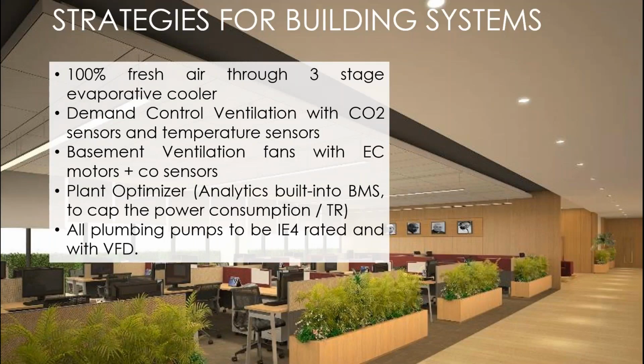also to add, when we talk about variable frequency drives, in indoor air handling units they have VFDs, we are all aware of that. On the fans we put VFDs, even on the pumps we put VFDs. In this building, in the air handling units, and also on the slide the basement ventilation fans, we have used something called an EC motor. What is an EC motor? It is like the fan regulator we used to have earlier in houses, which we can rotate from 0 to 100. It takes a complete turn from 0 to 360 degrees, and this is how the fans work. So you completely remove the need for a variable frequency drive.